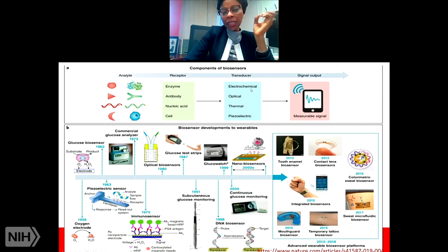So let's say that we have a glucose sensor, which is the most common that a lot of people can recognize, although biosensors extend way beyond that. The glucose monitor device is an electrochemical sensor. And essentially what it's doing is it looks at the glucose level. There's an electrode. An electrode is a conductor, like platinum or aluminum. And so on this electrode, which is going to be the transducer, you would have a very small layer of an enzyme called maybe glucose oxidase. So the glucose oxidase is the receptor, and the electrode is the transducer. And the analyte of interest will be the glucose. And so you can look at the glucose biosensor.